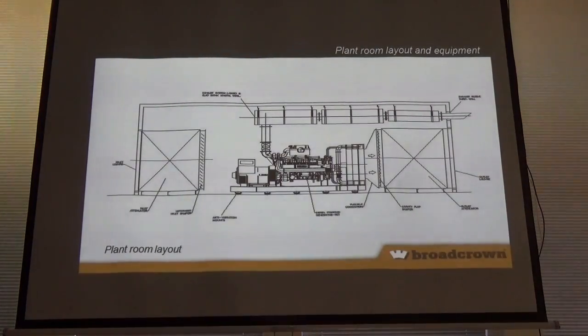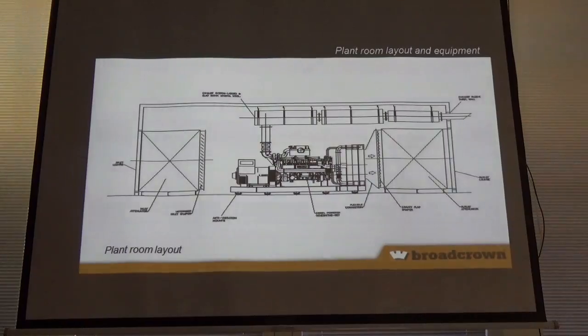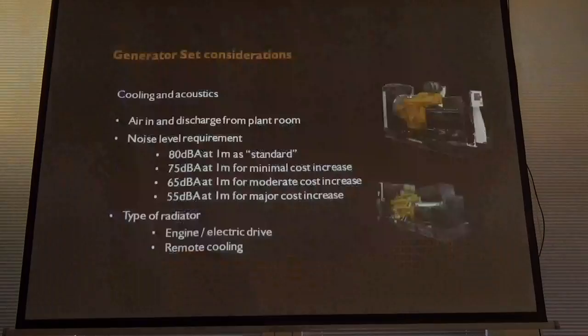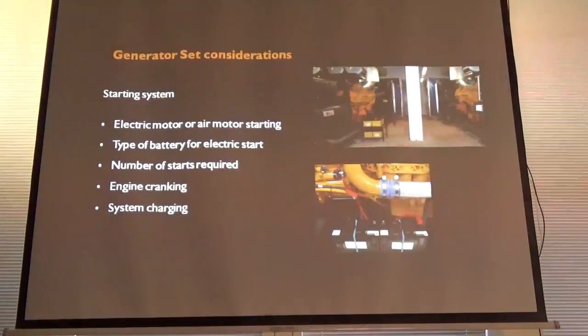But when those sets start up, there is always normally a big plume of black soot smoke. The reason why is because it's banging the maximum amount of fuel it can in those cylinders to start that unit up as quick as possible, because it's an emergency unit, simple as that. And that will clear, it'll stabilise very quickly. You can have low smoke starting systems, but at the end of the day, that's a compromise on how quickly that set gets up and running and ready to take load.